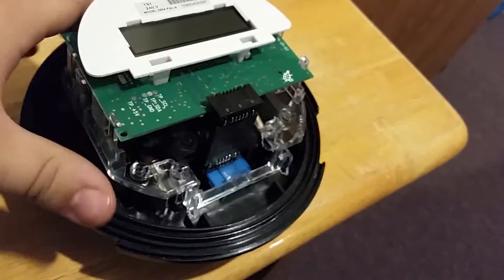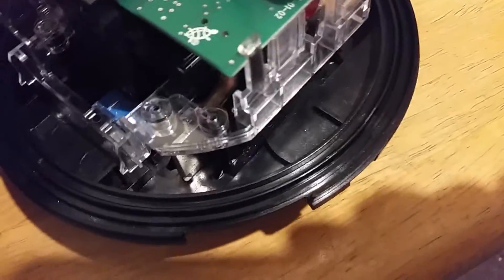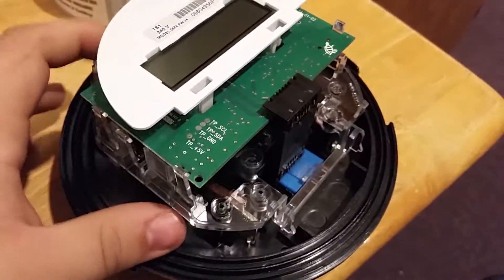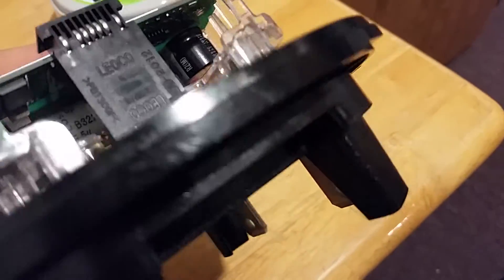Because it is a self-contained meter, there are no external CTs. It's pretty basic. I don't really want to tear it down too much past this. You can see in there — that's nice copper. It almost looks like heat pipes, but that's just solid copper conductors going through the CT.